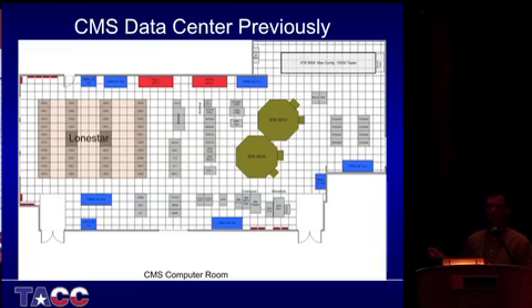You notice we got rid of some of the old CRAC units and repositioned some of our 40-ton CRAC units, and we tried to put them at the ends of the hot aisles so that the hot air would immediately go into them. Of course, we have perforated tiles in all the cold aisles.